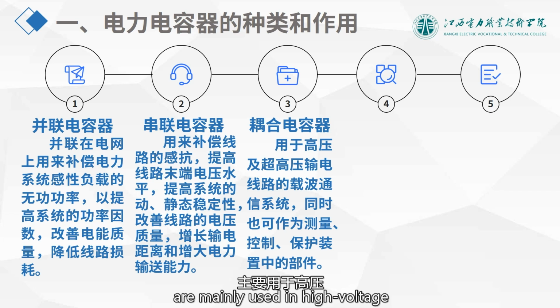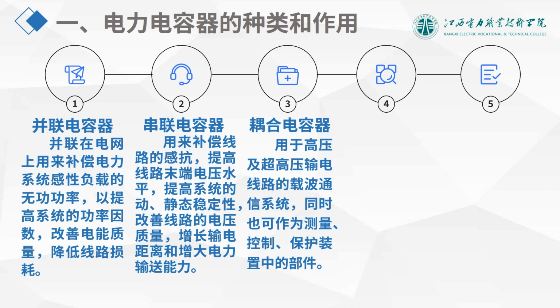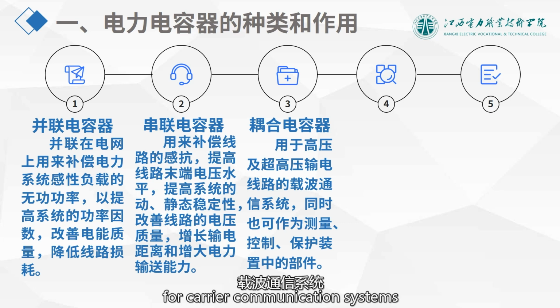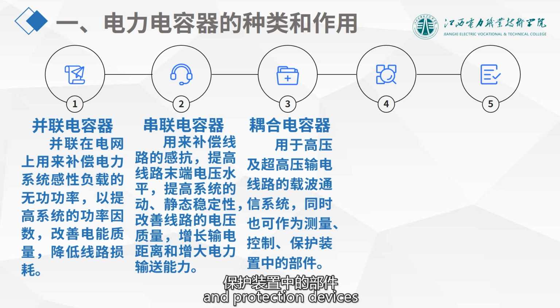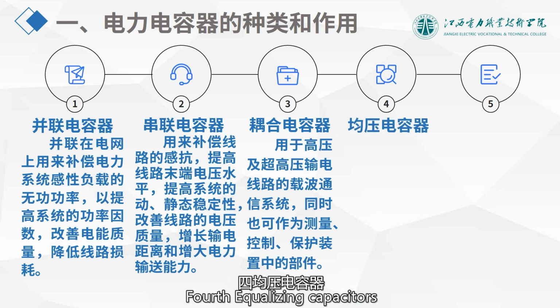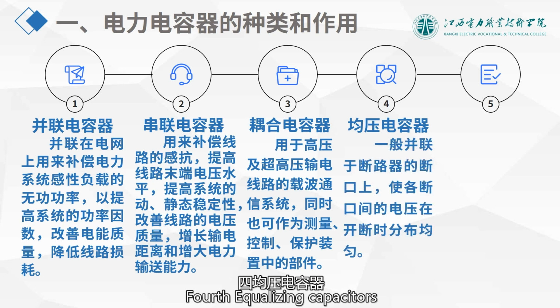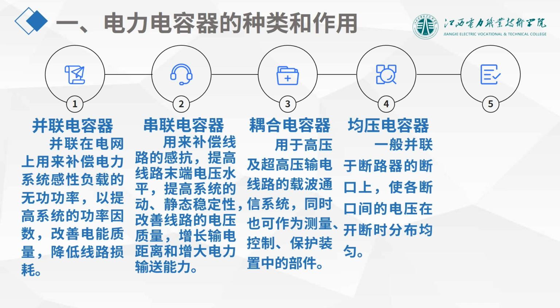Coupling capacitors are mainly used in high voltage and ultra-high voltage transmission lines for carrier communication systems. They can also be used as components in measurement, control, and protection devices. Fourth, equalizing capacitors. Equalizing capacitors are generally connected in parallel across the breaker contact to ensure that the voltage across each contact is evenly distributed when breaking.